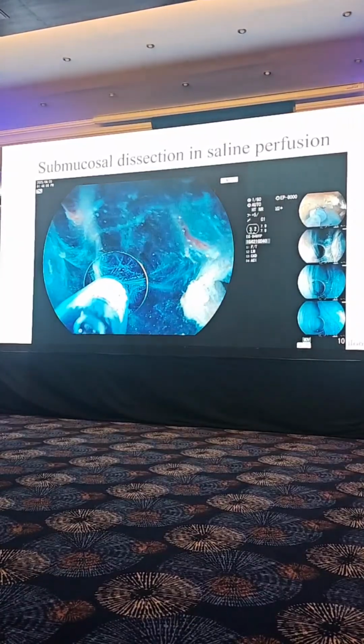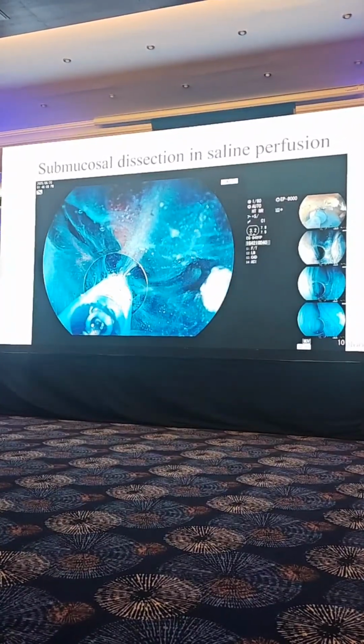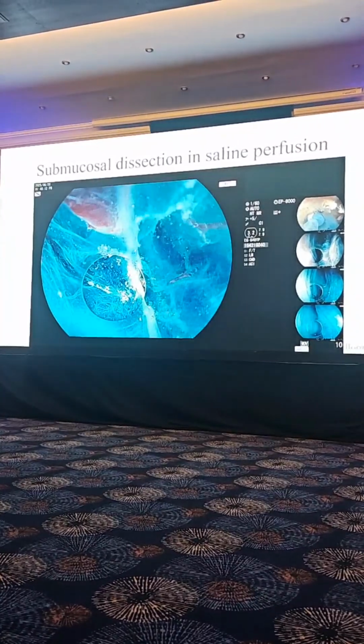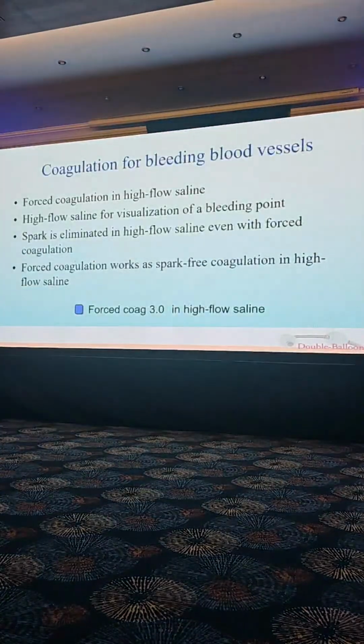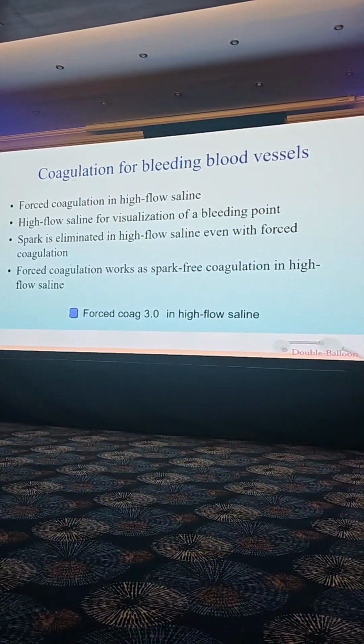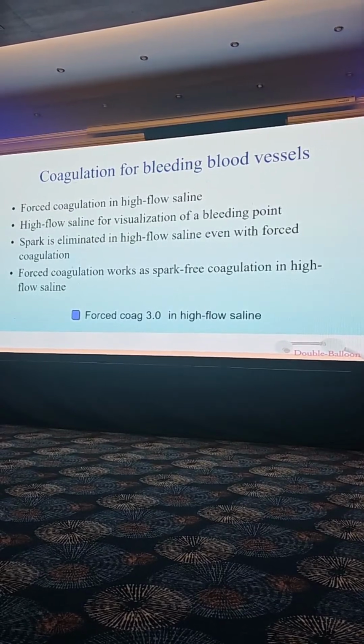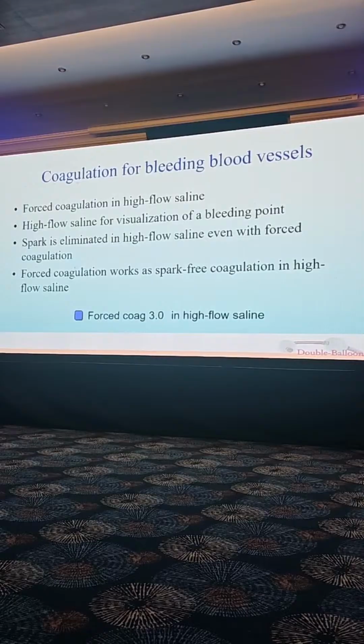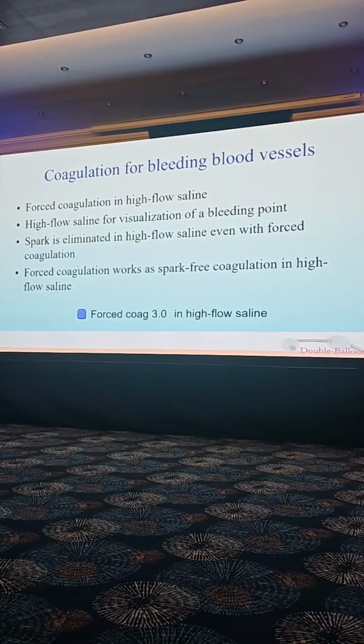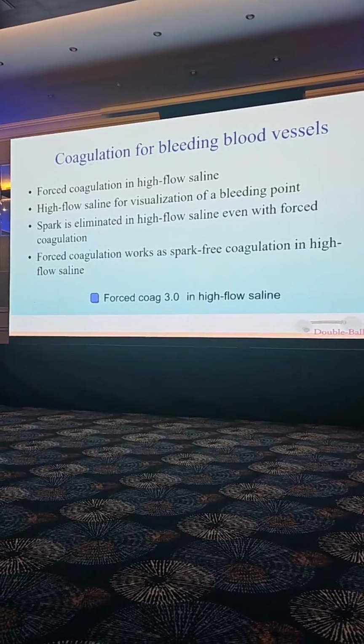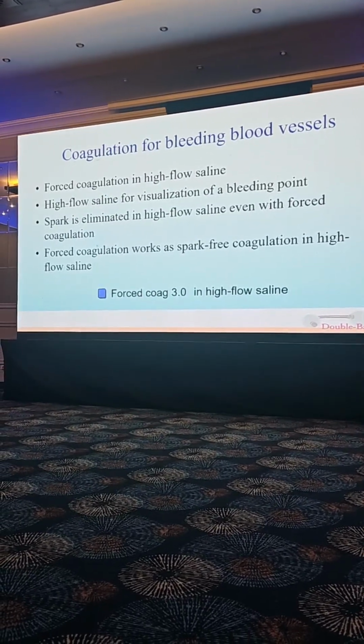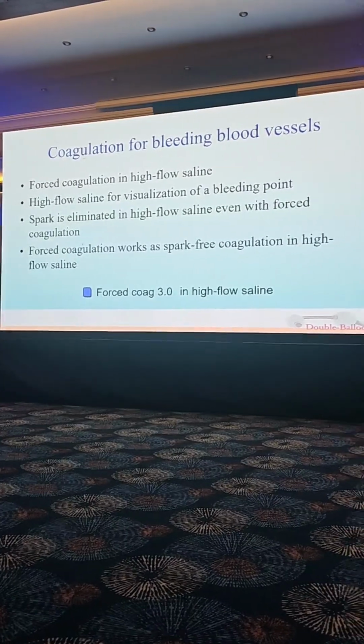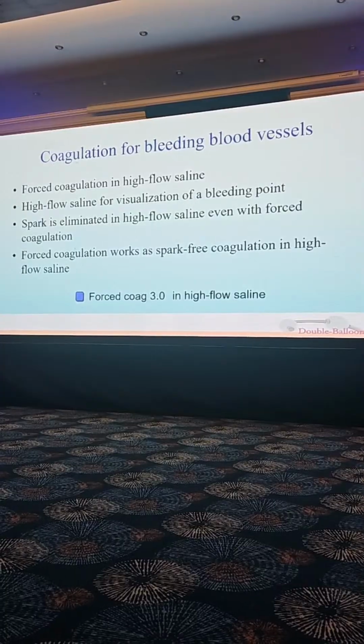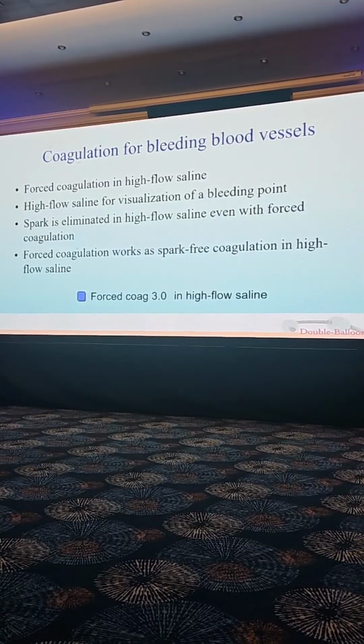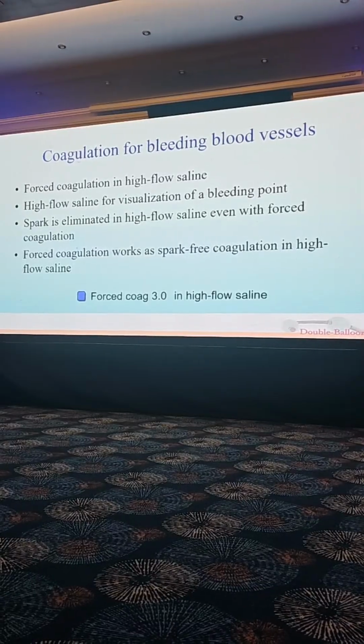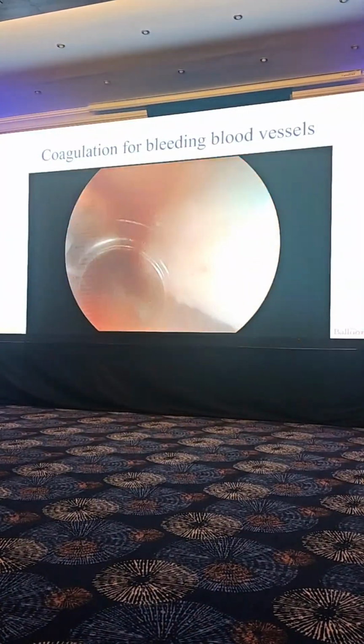And if it bleeds a little bit, soft coagulation still works for the hemostasis, if that is a minor bleeding. But if there is a major bleeding, then we have to have a high flow saline, for visualization of the bleeding point. And with the high flow saline, spark is eliminated, even with high voltage mode, like forced coagulation. So if the soft coagulation is not good enough, then with high flow saline, I use forced coagulation. So this is an example of the bleeding case.